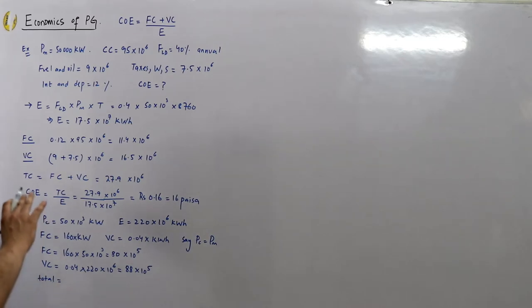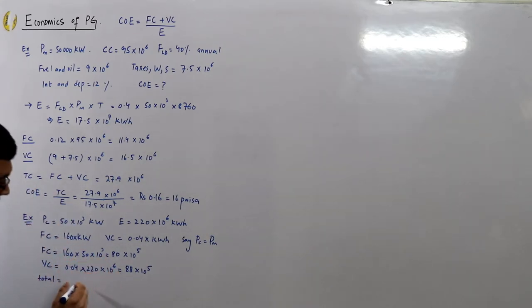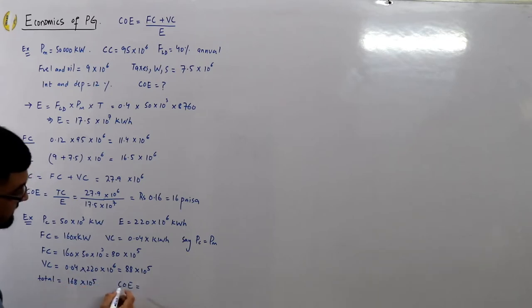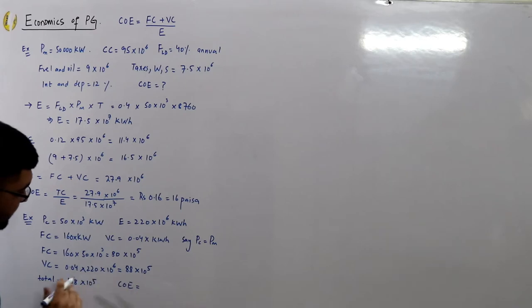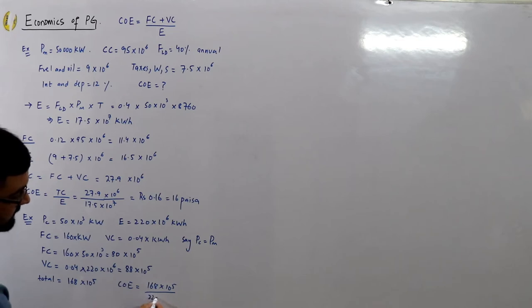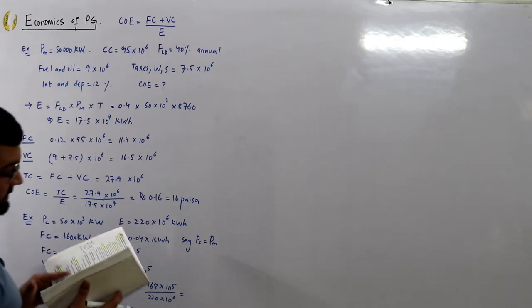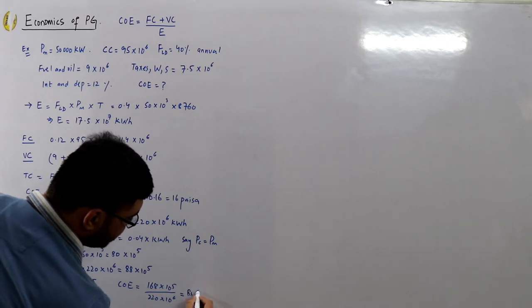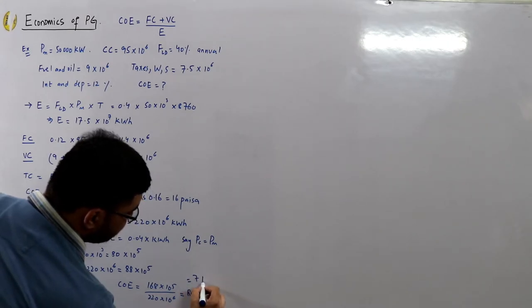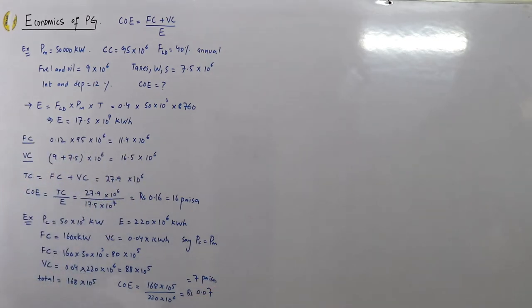Total annual charges = 80 + 88 = 168 × 10⁵ rupees. Cost of electricity per unit = 168 × 10⁵ ÷ 220 × 10⁶ = rupees 0.07, or 7 paise per unit.